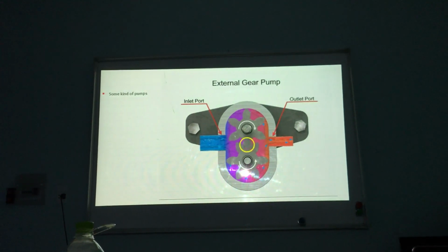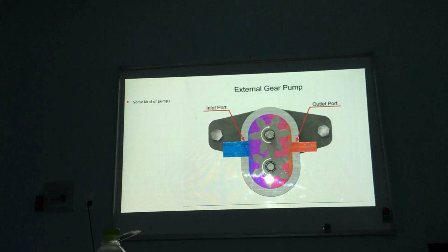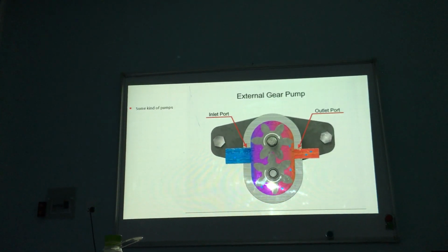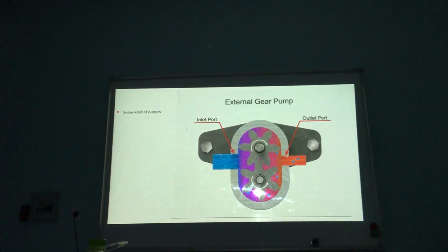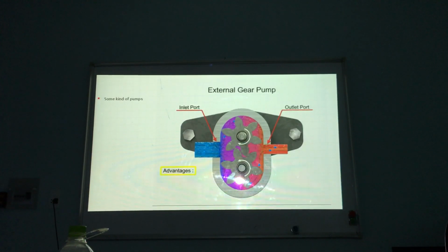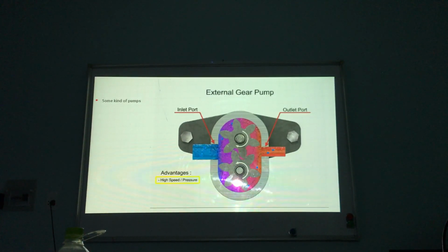As the gears rotate, a flow path is created around the outside of each gear. The fluid trapped in the slot between teeth is carried around and discharged into the cavity at the outlet port, where the teeth mesh up in the center of the pump to seal the outlet port from the inlet port, so no fluid passes between the gears.